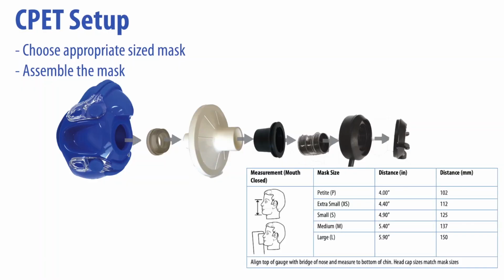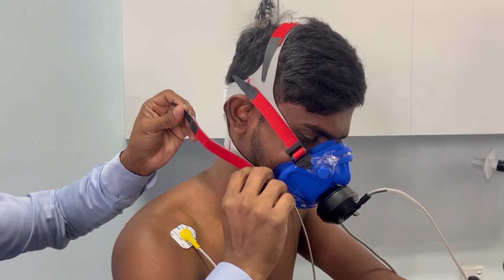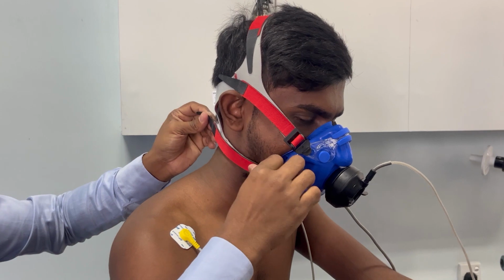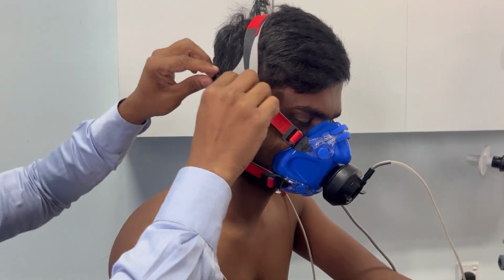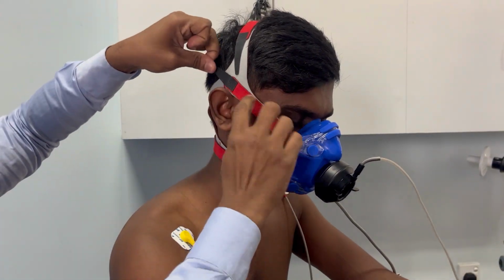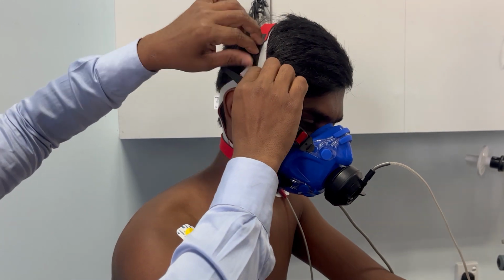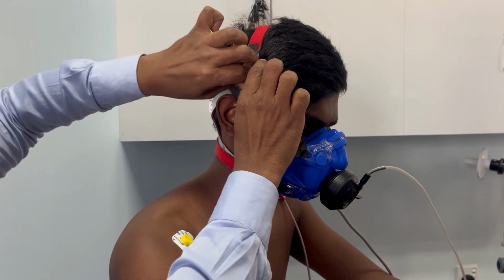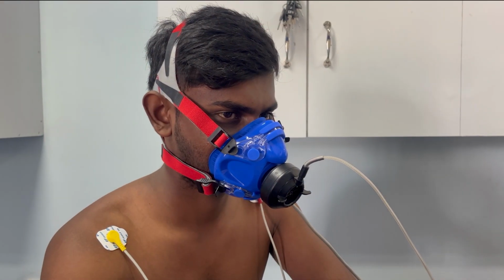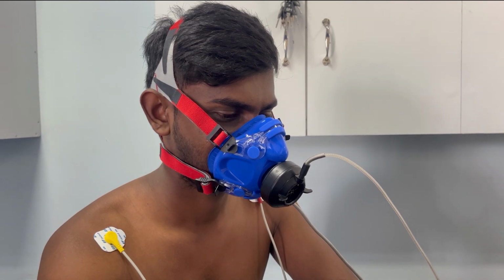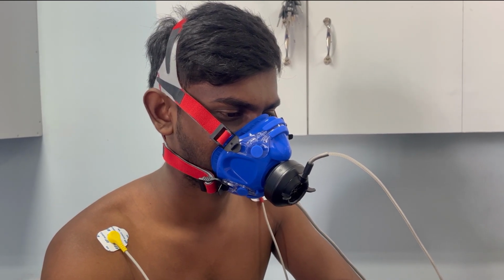Here we can see the order that the mask needs to be fitted to the filter and the sensors. To select the appropriate mask size, we measure the distance from the bridge of the nose to the bottom of the chin with the mouth closed. Then we need to fasten the mask properly with belts provided so that it is not leaking and not too tight to the patient as well.